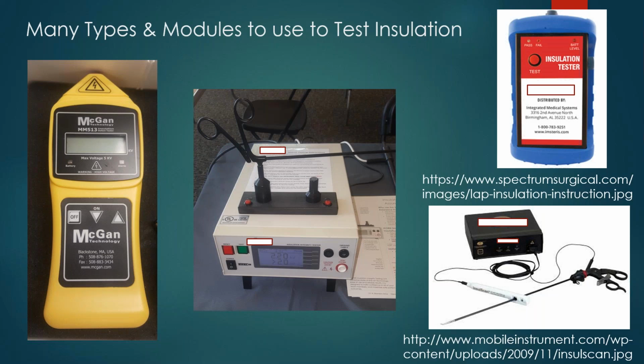Also, the insulation tester might need PMs. So what does that look like on the preventive maintenance? Is it something that's yearly? Does it have to have a yearly calibration? Does the tester need to be sent back to the vendor for the maintenance piece of it? And if so, do they provide a loaner? Or does it just go to your biomedical department? So again, some questions to ask.